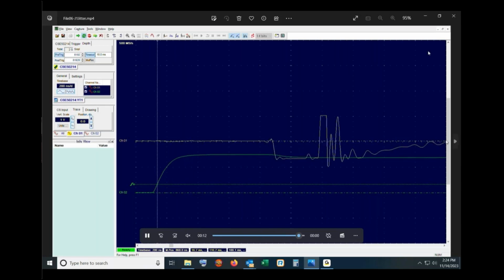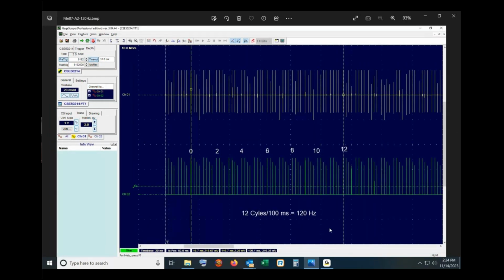Here we're looking at the full sampling rate of 500 megasamples per second. We're only looking at about 2 or 3 microseconds worth of signal. So in order to understand this noise, I decreased the sampling rate and increased the number of points from 8192 to 8 million. By doing that, we've increased the acquisition time from a few microseconds to, I guess, 100 or so milliseconds. So that's a time scale de-zooming factor of 10,000.